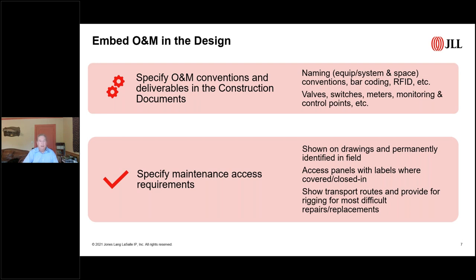You have to specify maintenance access in the drawings, actually showing the path to get the largest piece of equipment in and out of a room. In some cases, if 3 feet of clearance is required in front of equipment, you can mark that area on the floor with paint or tape so people don't stack equipment or parts there.